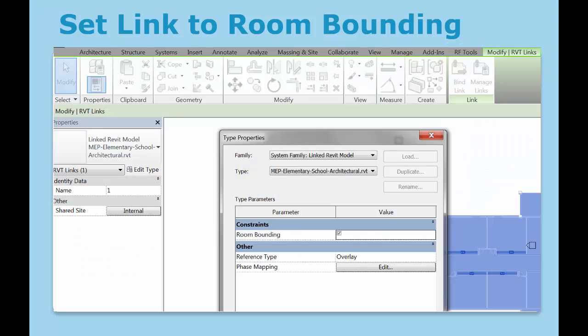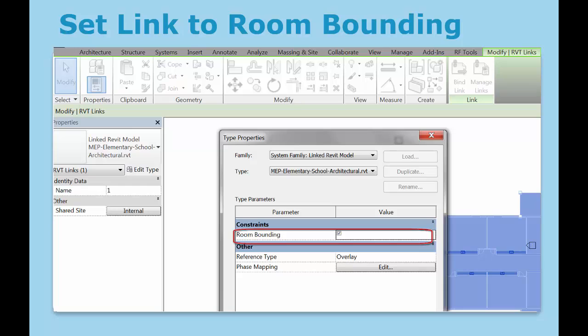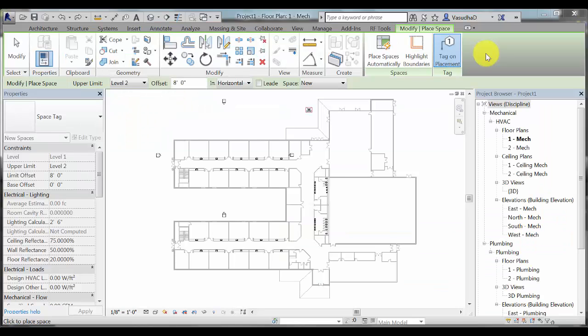In Revit, once you have linked in the architectural file within your project, spaces need to be created first in order to accomplish an accurate heating and cooling load analysis. Spaces are defined by the same elements that define a room from your architectural link model. Hence, you want to make sure that your link file is set to room bounding before going about placing spaces. In this project, I have linked in the architectural file and set the constraint to room bounding.